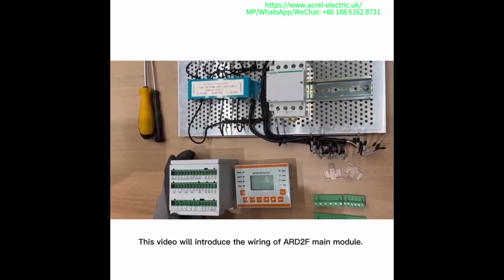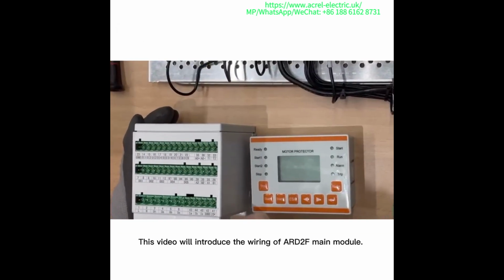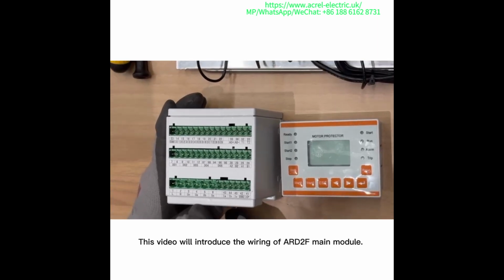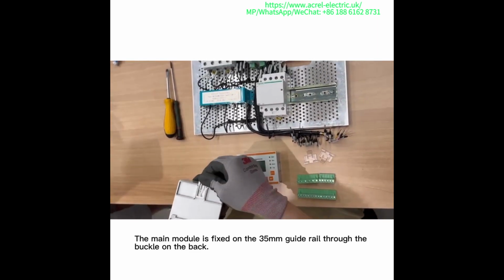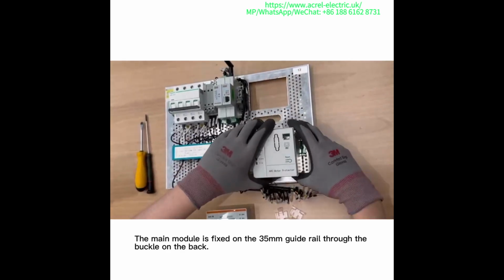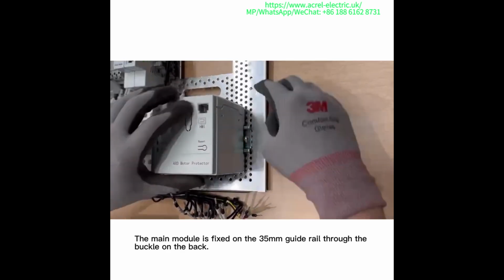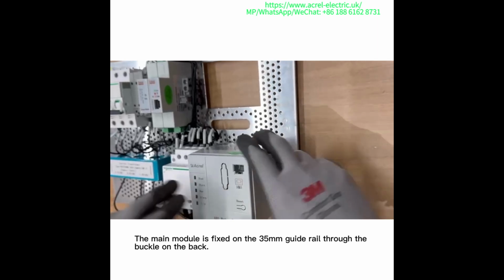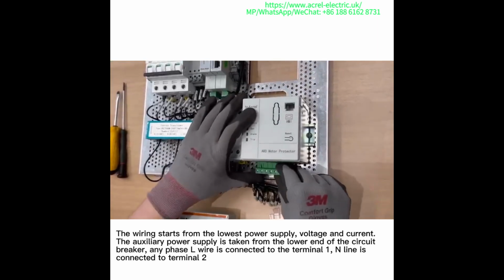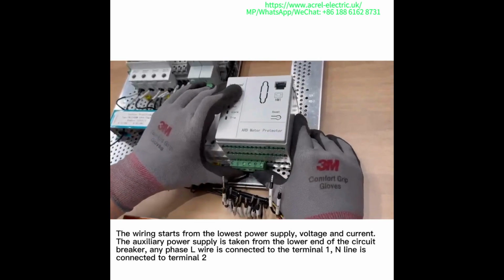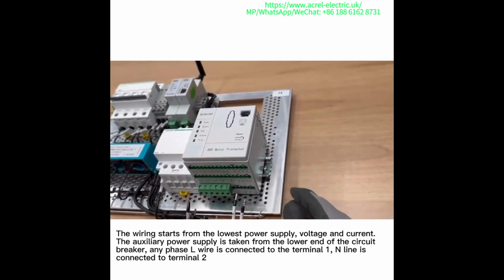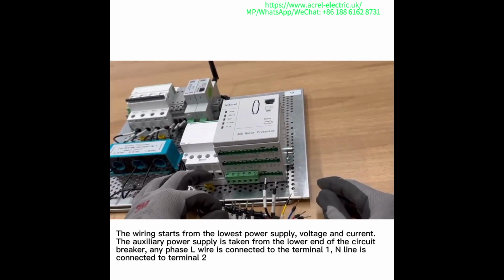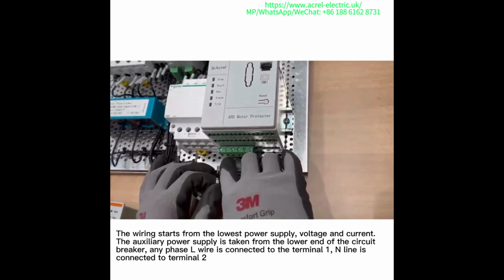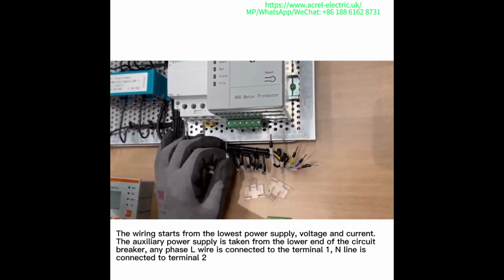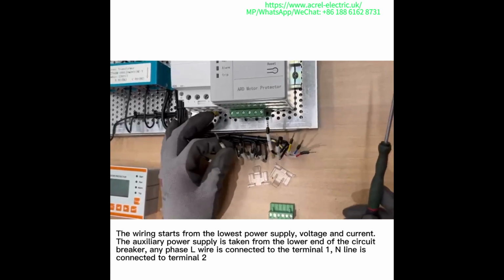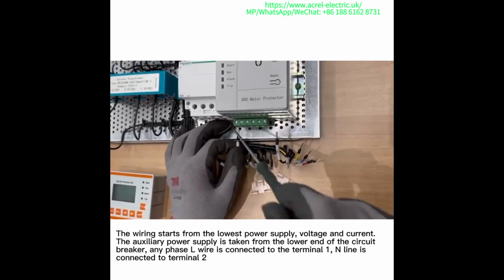This video will introduce the wiring of ARD2F main module. The main module is fixed on the 35mm guide rail through the buckle on the back. The wiring starts from the lowest power supply, voltage and current. The auxiliary power supply is taken from the lower end of the circuit breaker. Any phase L wire is connected to terminal 1 and N line is connected to terminal 2.